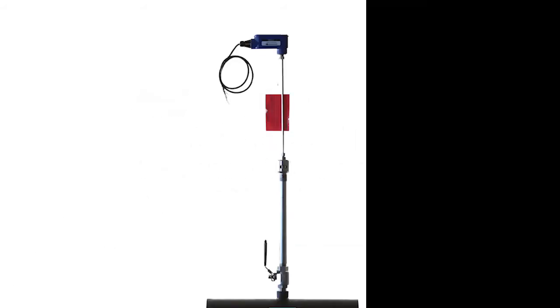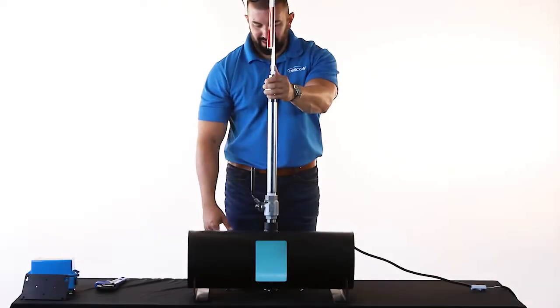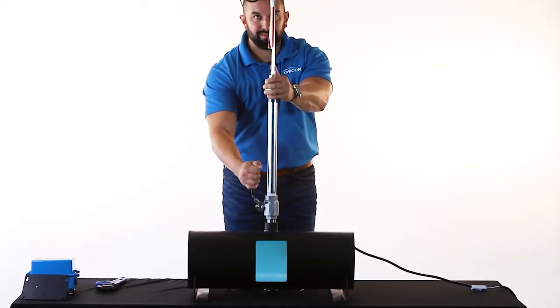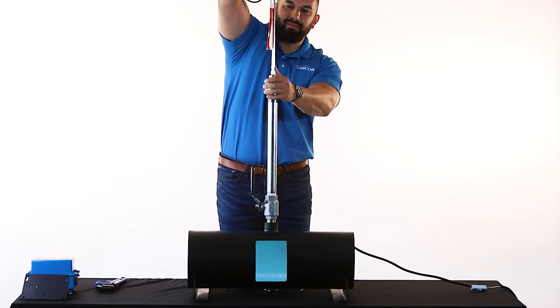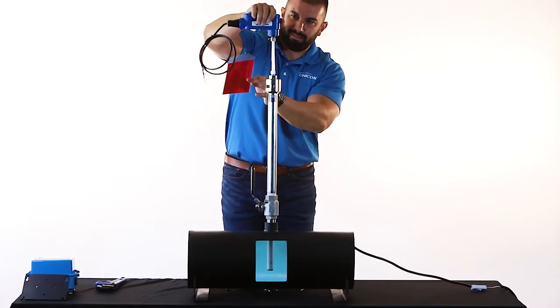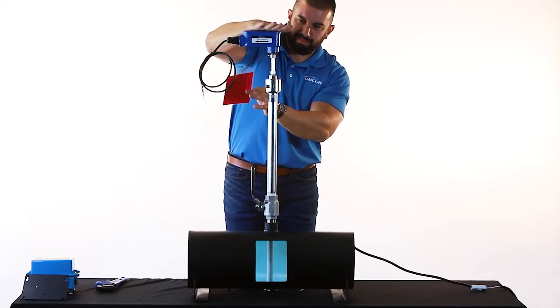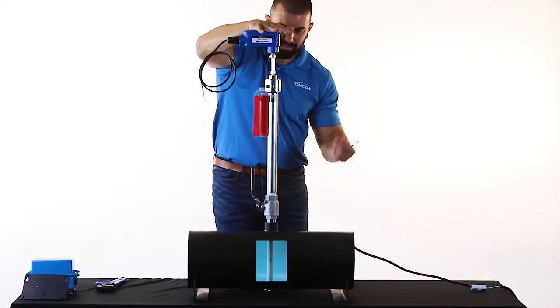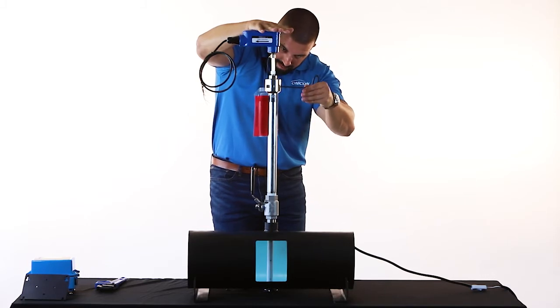Once the hot tap adapter has been installed into the isolation valve, confirm the valve has been fully opened before inserting the flow sensor into the pipe. As you insert the sensor, use the enclosure to align the flow meter with the pipe and continue to apply and maintain downward force on the flow meter even after the foot has contacted the far side of the pipe.